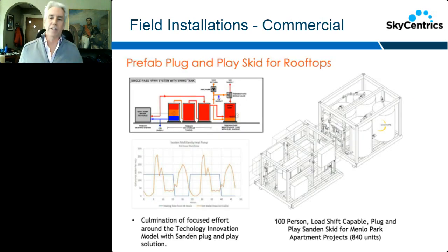Let's also talk about field installation of commercial skids. So yesterday, Mitsubishi presented, Sanden has presented in the past, and we're helping Mitsubishi, Sanden, and others give a CTA port kit that can actually retrofit to their system controllers and give a CTA-2045 port so that we can plug in our cellular module. So imagine this kit going on commercial building rooftops, and you plug in the kit, you plug in the cellular module, and you instantly have grid control. And we're also feeding about 200 points of data from the skid out to our cloud for delivery to Ecotope and others for really monitoring these new commercial heat pump systems. So that's really exciting, and we're excited about that.